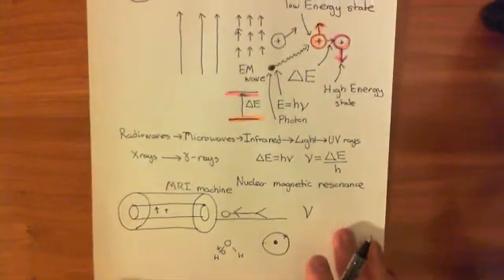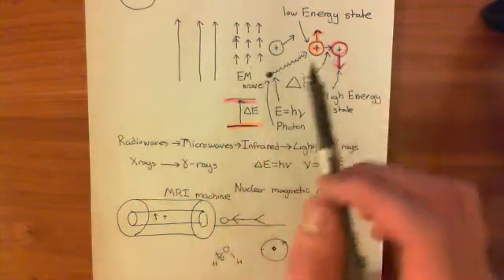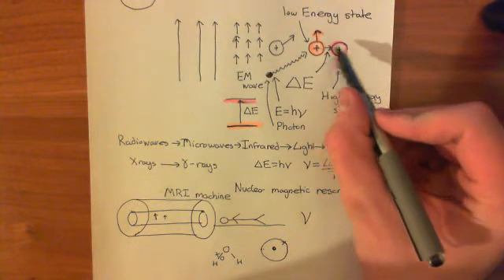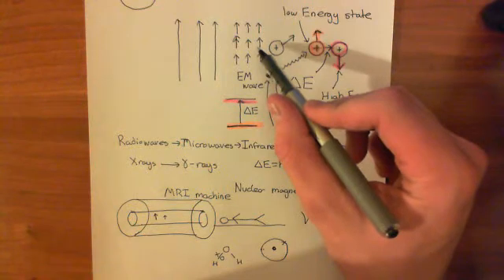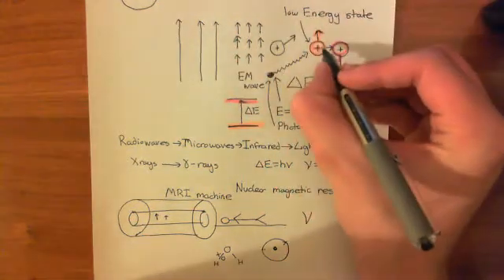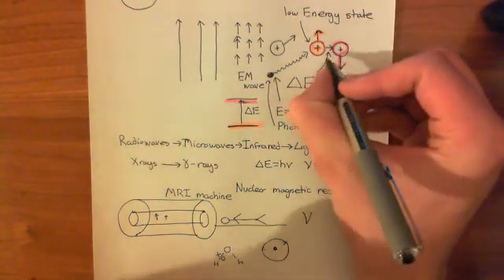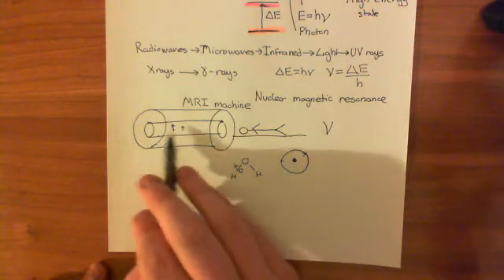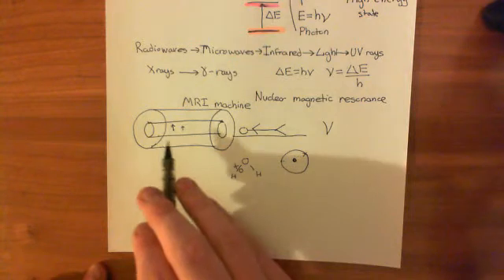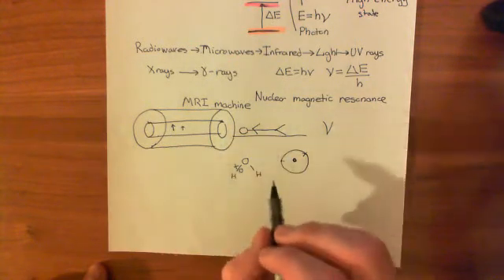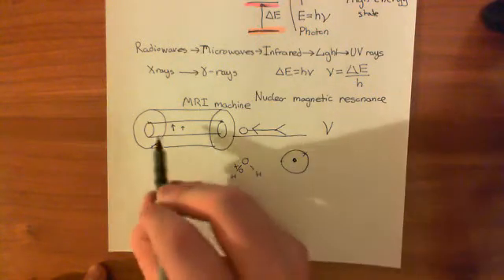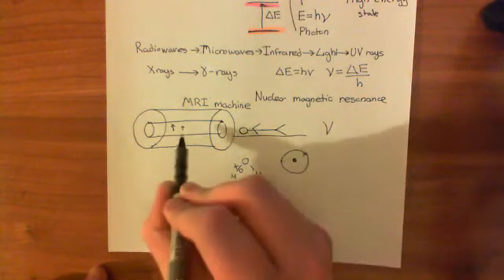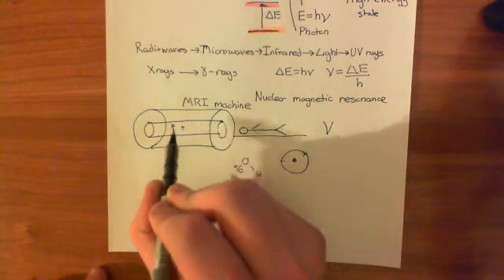This is something I should stress: the energy difference between the low energy state and high energy state is dependent upon the strength of the external magnetic field. If the magnetic field is very, very strong, then the energy difference required to move the proton from having its magnetic dipole moment aligned to disaligned is going to be greater. So if we've made the magnetic field slightly different strengths throughout the MRI machine, the energy difference is going to be different everywhere. This fixed frequency will only work at a particular point where the magnetic field strength is just right.